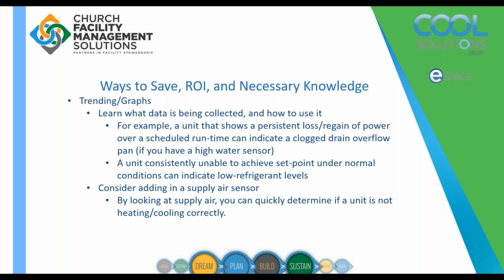But it is an often underutilized option for facilities, being able to look at the supply air versus the room air. Because when we put these thermostats in these big rooms, they're not always in the most ideal spot, and it's not always giving us the information that we need. So check that supply air sensor. It's a great way. Consider it down the road.